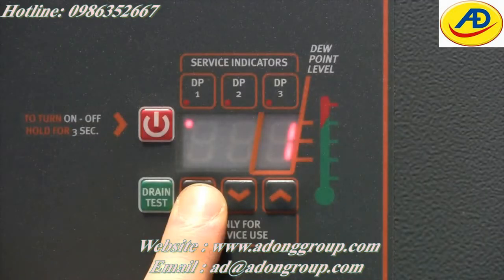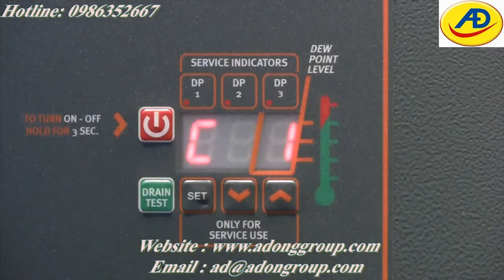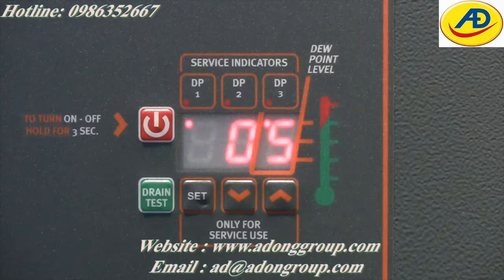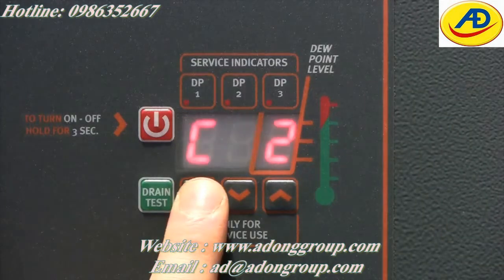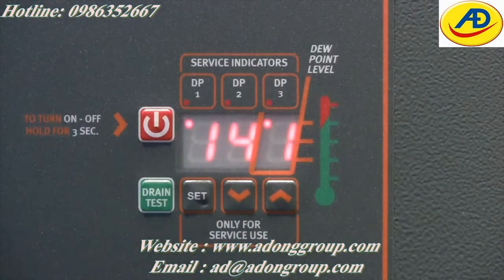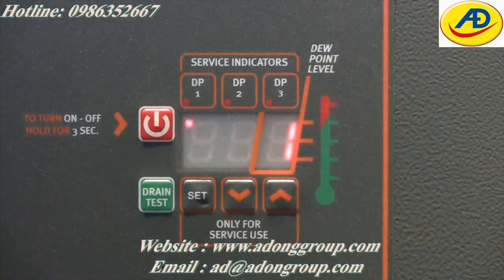Once the board is unlocked, press and hold the set button for 10 seconds until C1 is displayed. C1 will be visible on the readout, followed by a value for C1. Pressing the set button a second time will make C2 visible on the readout, followed by a value for C2. Go through all the parameters, making note of both the C number and the corresponding value.